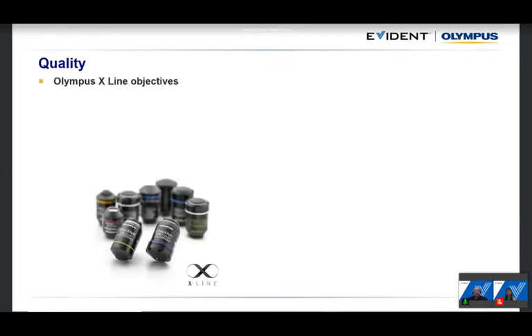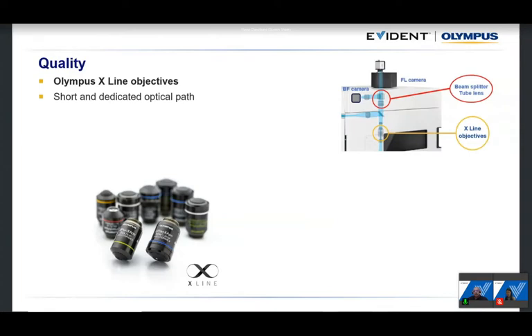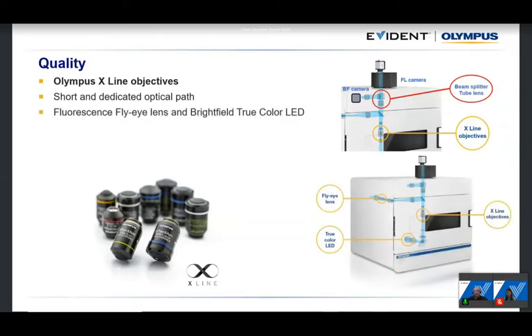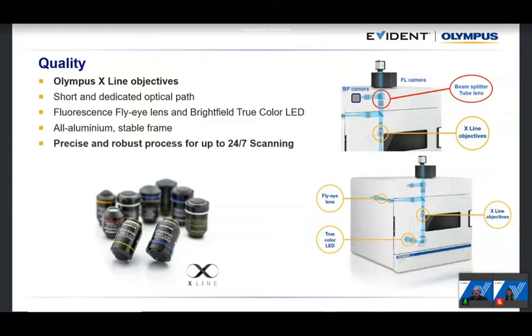Speaking of quality: the VS200 is based on our best Olympus X Line objectives, providing great corrections and image quality. We created a very short optical path between the objective and the camera to ensure the highest possible image quality. We also use fly-eye lenses and a true-color LED that doesn't distort staining colors, especially in brightfield. An all-aluminium stable frame makes the system robust and precise, capable of scanning 24 hours a day, seven days a week without stopping.